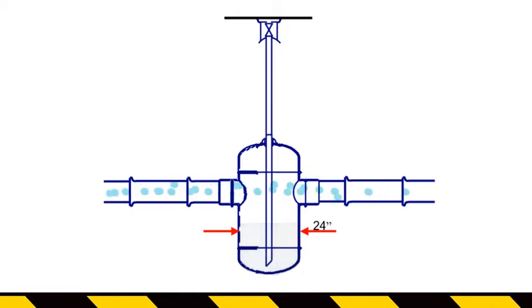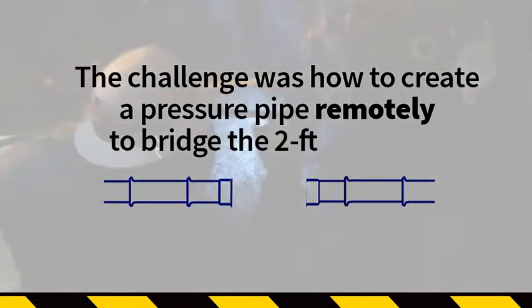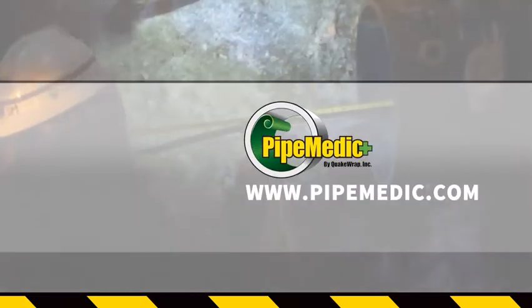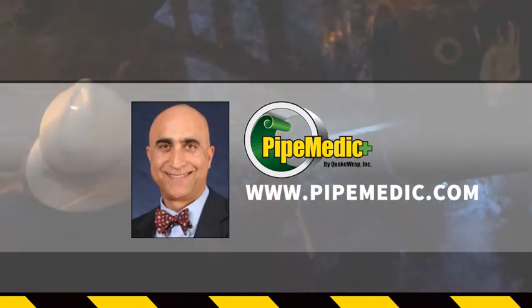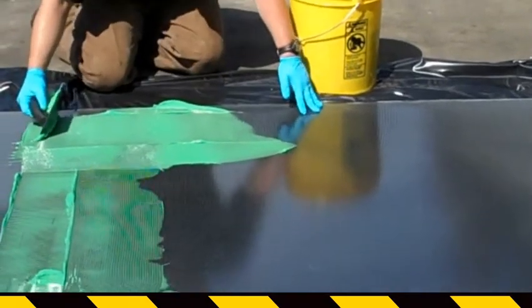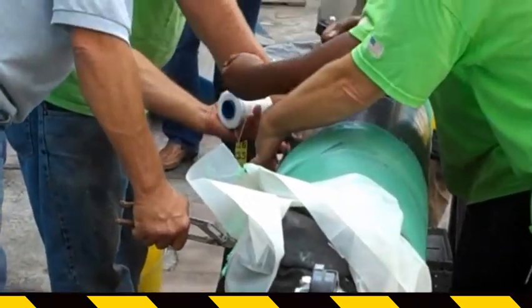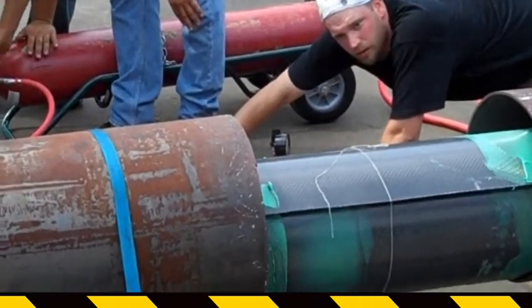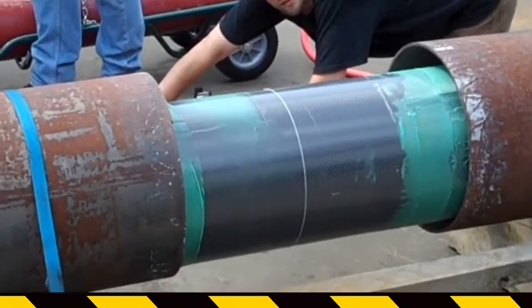The non-structural liner requires the support from the host pipe. At the location of the drip pot, the liner could blow out. The challenge was how to create a pressure pipe remotely to bridge the 2-foot-wide gap. PSE&G decided to use the PipeMedic Super Laminate recently developed by Professor Mouasani. As shown in this test demonstration, the 4-foot-wide carbon laminate sheets are coated with epoxy and wrapped around a packer device. The assembly is sent into the pipe and positioned using closed-circuit TV cameras. As the packer is inflated, the PipeMedic Laminate unravels and creates a very strong liner that is only 0.1-inch thick and spans across the 2-foot gap.